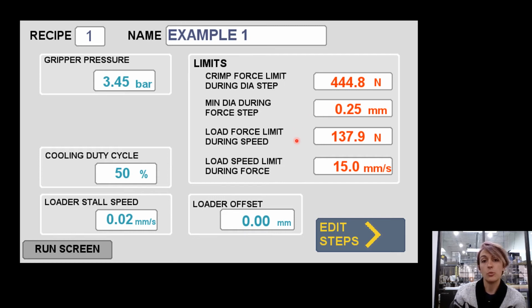Similarly, for the auto pushrod loader, we have some limitations as well. If you're using a load speed step, which controls the speed of the loader, but not the force, you may want to limit the force that your stent experiences. On the other hand, if you are using a force controlled step, then you may want to limit the speed or the rate at which your loader travels while maintaining that force.